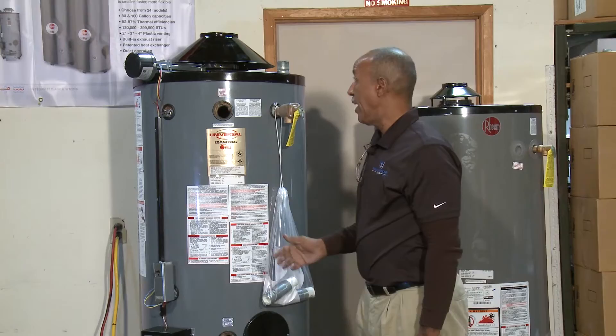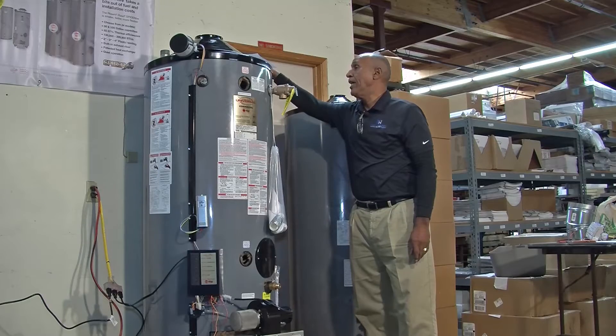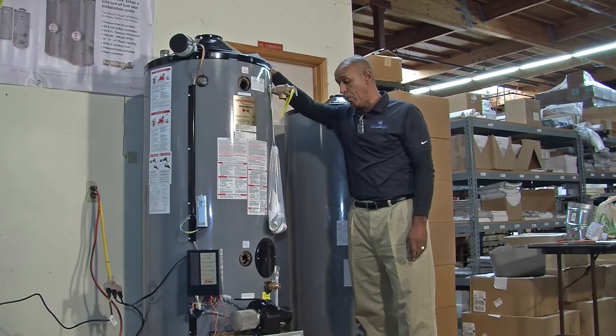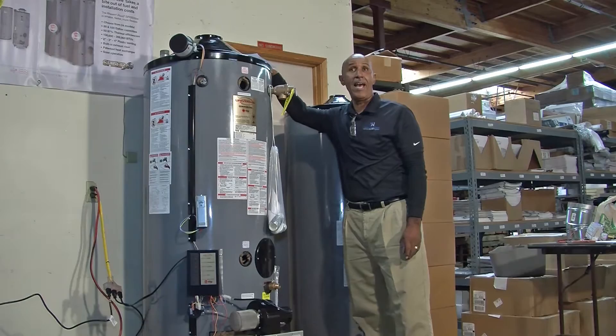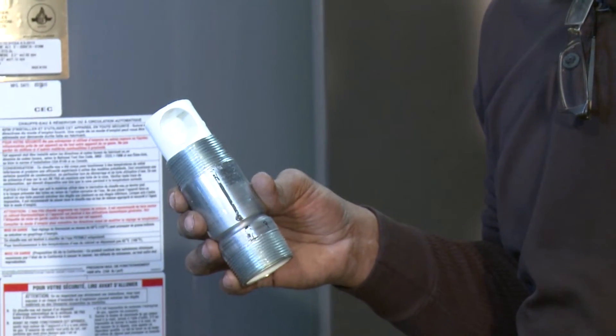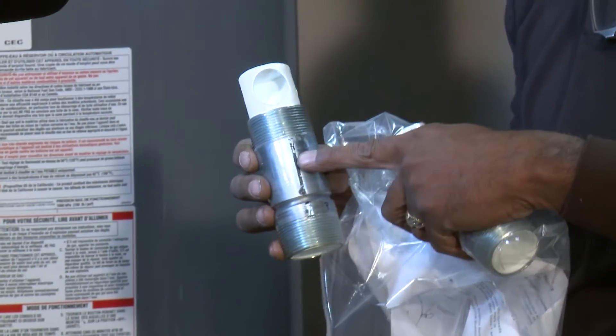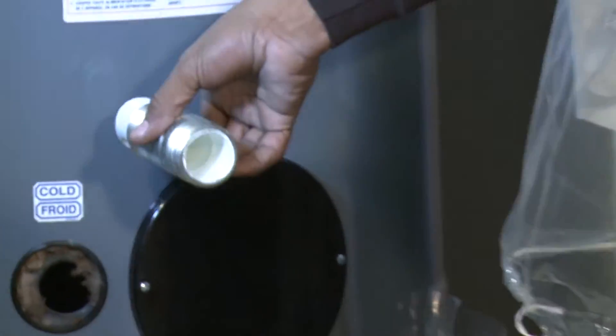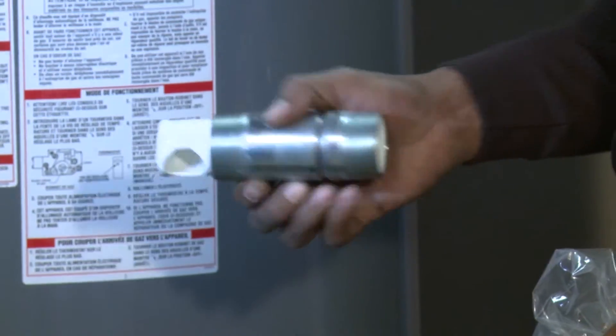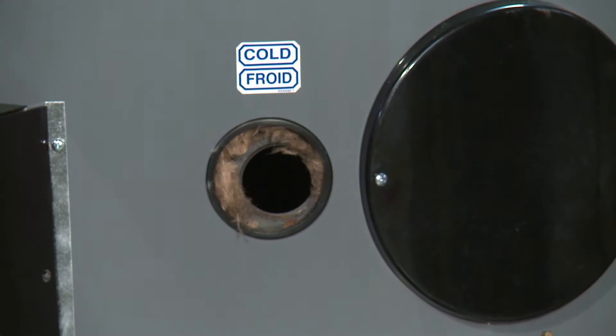This water heater has multiple water ports — two in the front, two on the top, and two in the back. It comes equipped with a dip tube that shoots water into the bottom of the water heater so it heats from the bottom up instead of from the top down. Rheem supplies a diffuser tube if you are going to use the side water ports. There is a mark on the bottom of the diffuser tube that should be pointing down so water flows into the bottom of the water heater.